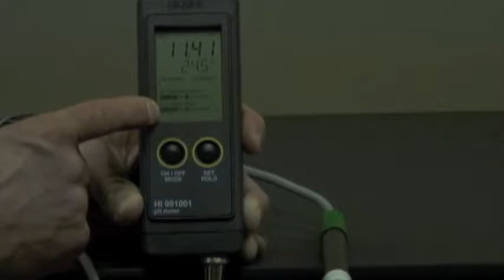Next, what I'm going to do is connect the electrode, put the batteries in, turn it on, and show you how it works. Now that I've connected the probe and put the batteries in, I'm going to turn the meter on. The first thing that's going to come up is the battery indicator energy level. When that's done flashing, it's going to go into the measurement mode. You're going to see the pH reading, the temperature, and a stability indicator. Now, a really nice feature about this meter is the fact that it has auto instructions. And there's 2 items here. Number 1 is for calibration, and the next one is for setup. I'm going to take you into the calibration mode next.